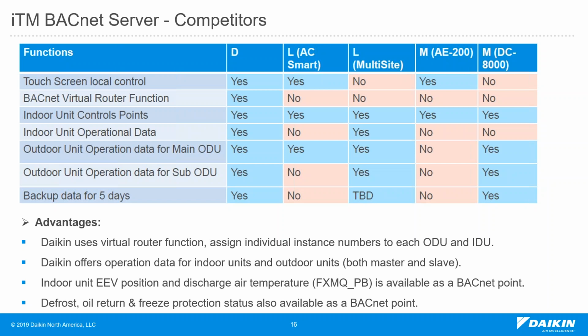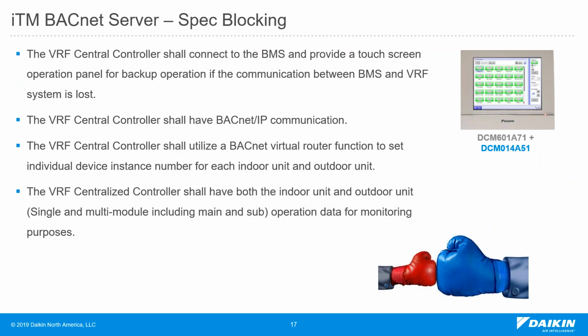Indoor unit EEV position and discharge air temperature for the FXMQ are also available as a BACnet point. Defrost, oil return, and freeze protection status are also available as BACnet points, and they vary based on the indoor unit, but all of those are available for the BMS integrator.